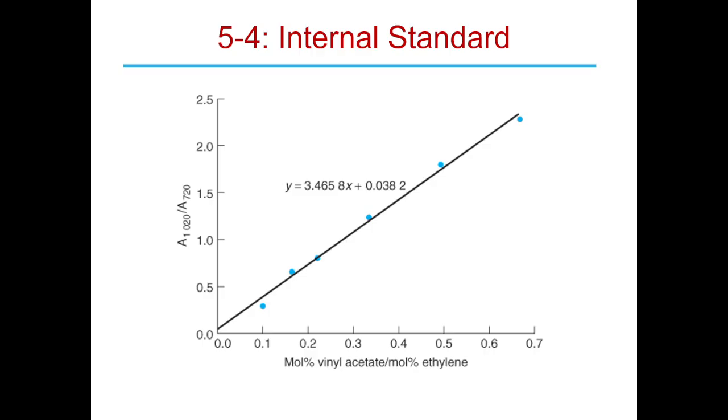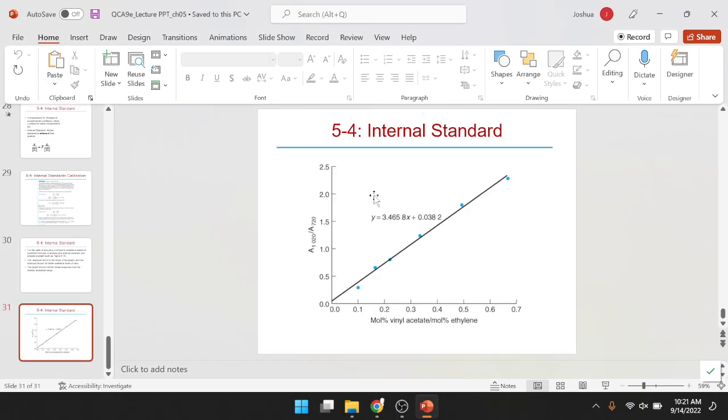This is not magic. The stuff done by NMRs is usually done by the instrument manufacturer, and you can do a calibration and redo it. It's not magic. It's not a black box. No hand waving and poof. It's not what happens. It's all done by people. They can screw up, and you can fix it. Okay?